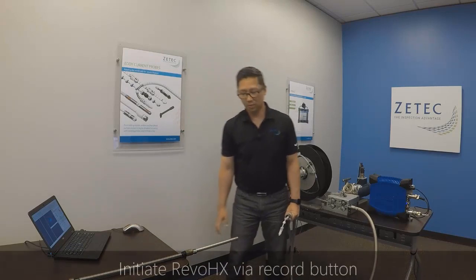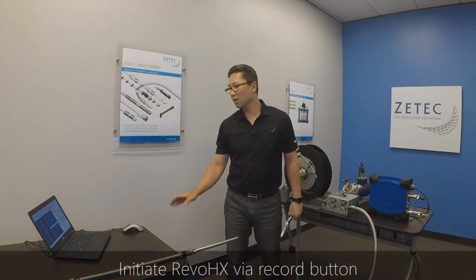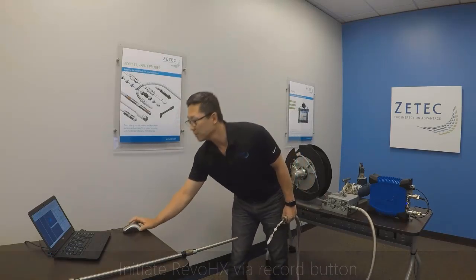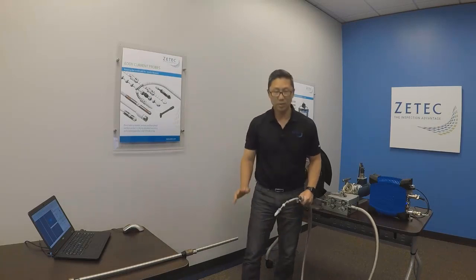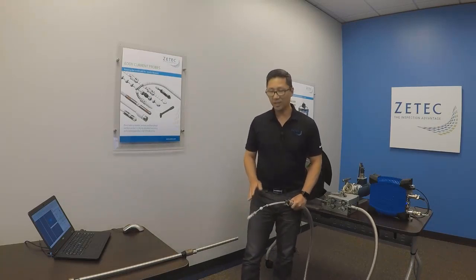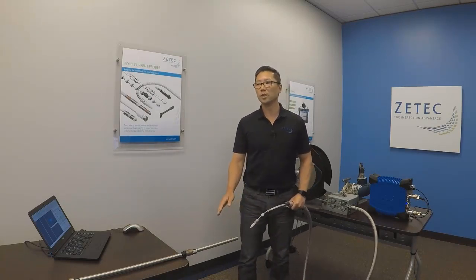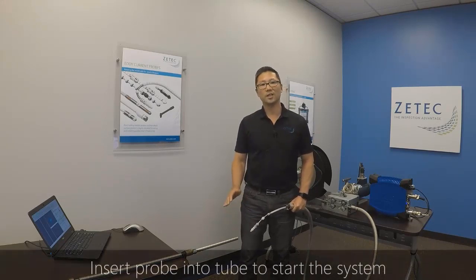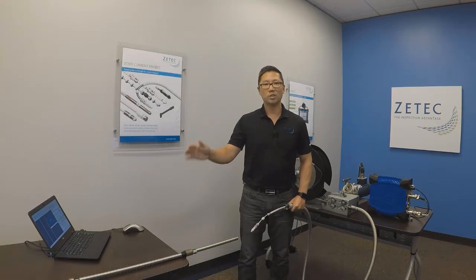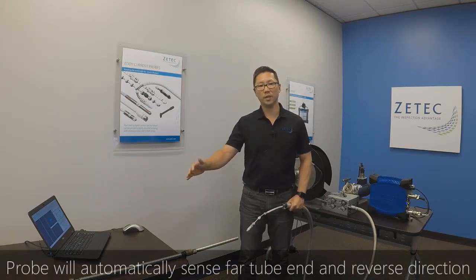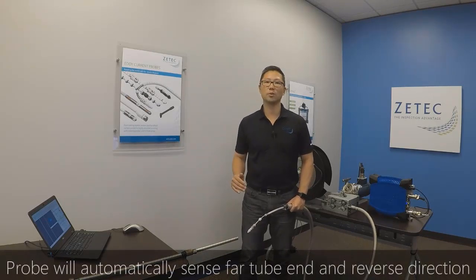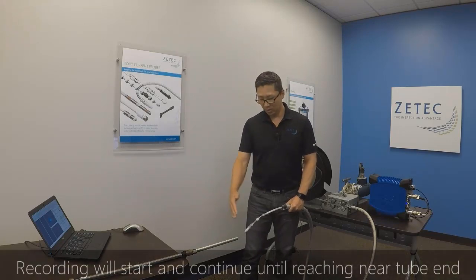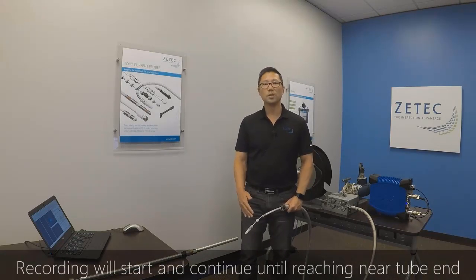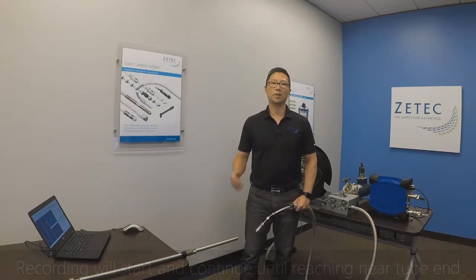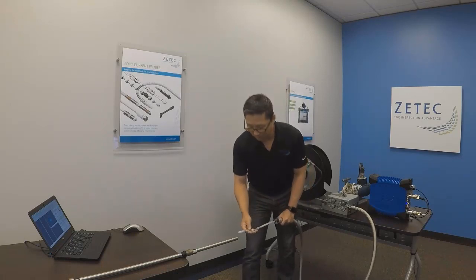Now to start the acquisition, all I have to do is press the record button, and now it's ready to start. Once I insert the probe into the tube, it will automatically detect that it's inside the tube and start going forward. Once it reaches the far tube end, it will stop and then start recording in the reverse direction. Once it reaches the near tube end, it will stop and then get ready for the next tube.